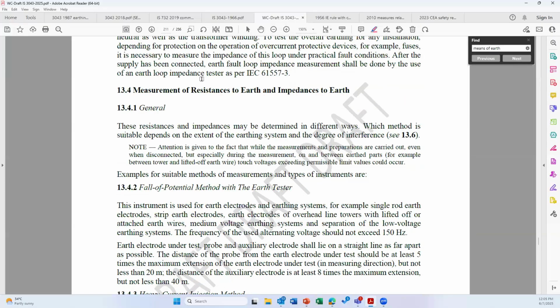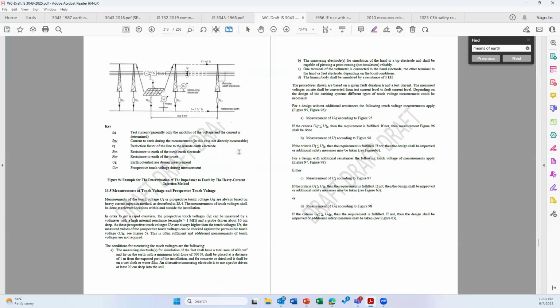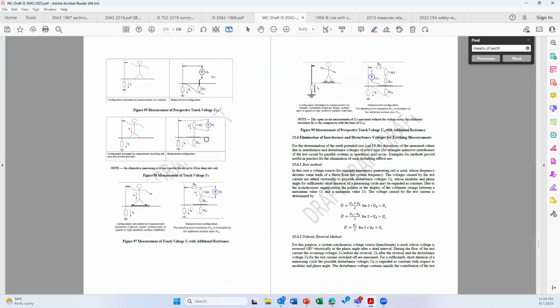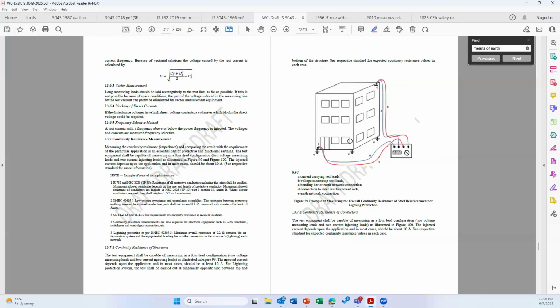Then the measurement of resistance and impedance to earth. This is based on the heavy current injection method. You have a current injection test kit, and you are injecting a current, and you are trying to find out the touch and step potential. These figures and information are included. Then the method of how to measure the prospective touch voltage, UVT, with additional resistances is included.